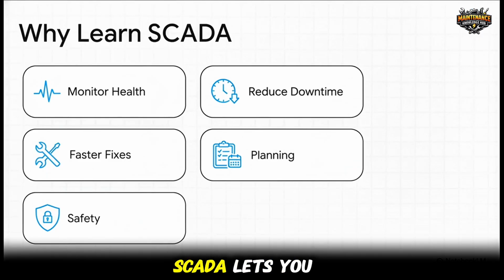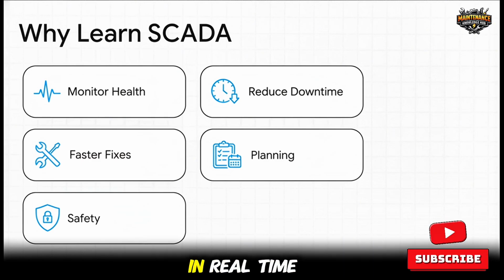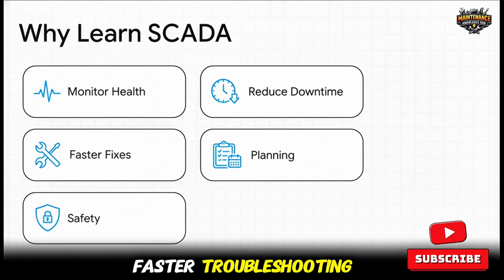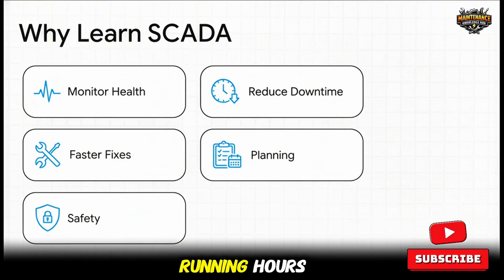Well, first off, SCADA lets you monitor equipment health — things like bearing temperatures and vibration in real time. It provides instant alarms to drastically reduce downtime. It tells you exactly what failed and when, giving you much faster troubleshooting. It continuously records running hours to improve your maintenance planning. It increases plant safety with automatic shutdowns, and it improves energy efficiency by carefully tracking power and fuel usage.